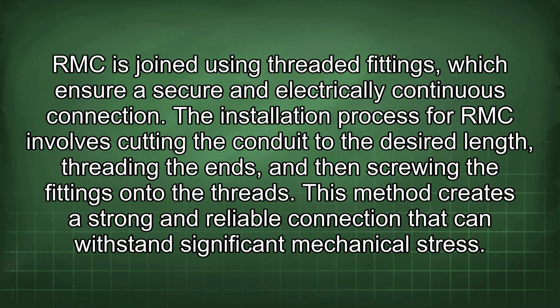RMC is joined using threaded fittings, which ensure a secure and electrically continuous connection. The installation process for RMC involves cutting the conduit to the desired length, threading the ends, and then screwing the fittings onto the threads. This method creates a strong and reliable connection that can withstand significant mechanical stress.